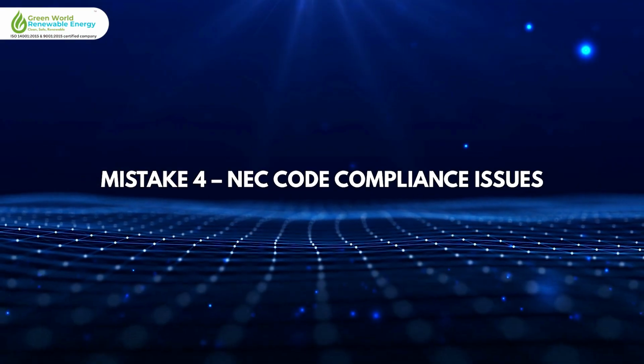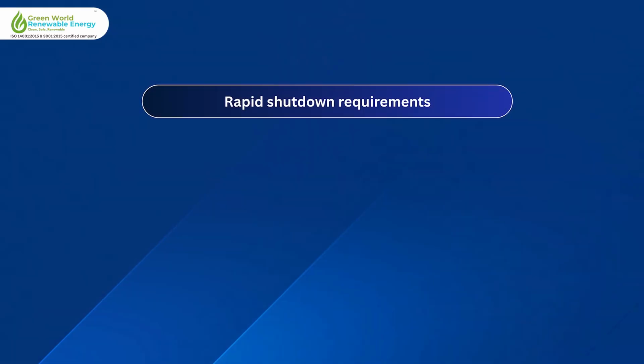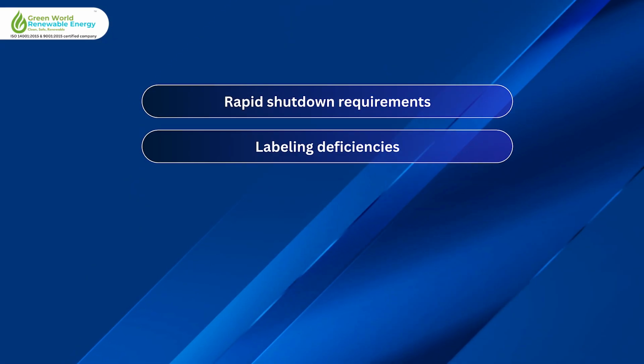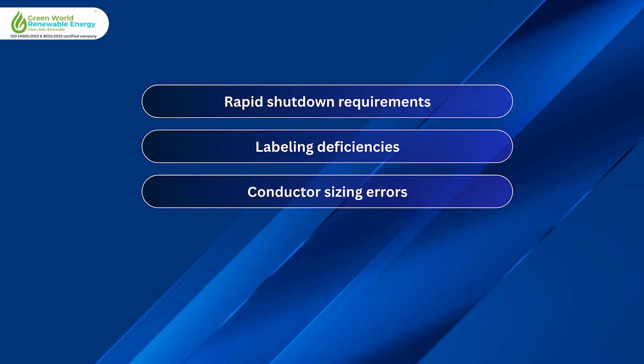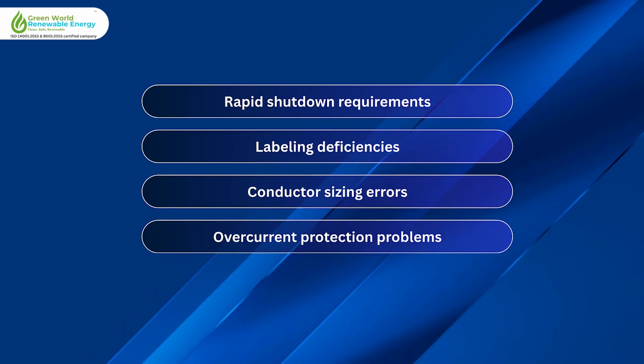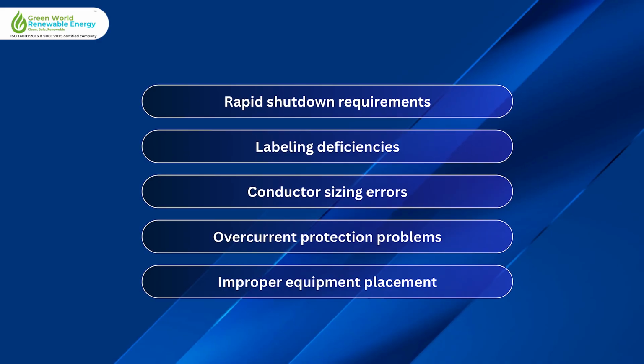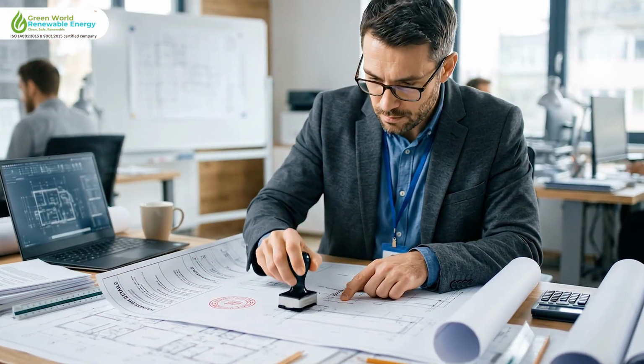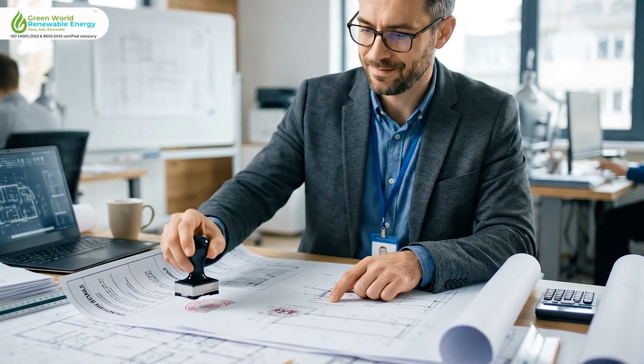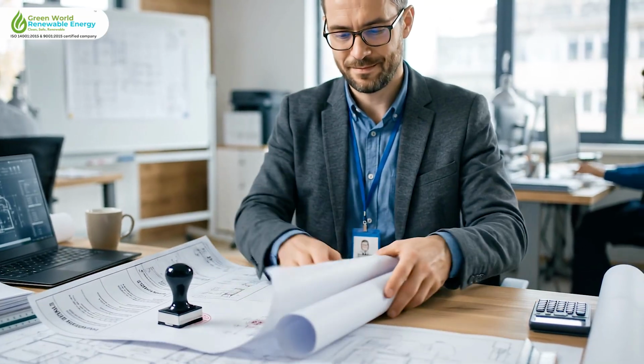Mistake 4: NEC code compliance issues. The National Electrical Code continues to evolve. Many rejected plans involve code compliance issues such as rapid shutdown requirements, labeling deficiencies, conductor sizing errors, overcurrent protection problems, and improper equipment placement. Different jurisdictions may adopt different NEC editions, so a design compliant in one area may require modifications elsewhere. That's why permit plans should always be reviewed against local AHJ requirements before submission.